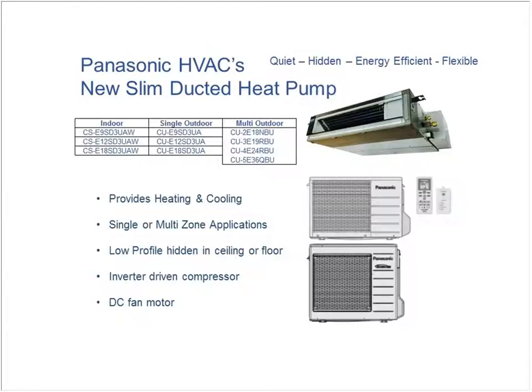Oh, and this is probably the best application. The issue with this application, though, is there's a cost issue. This is a slim ducted heat pump, and we met with Lennar Homes and several builders who are actually building this into their architectural design. So what happens with the slim duct is that this has an exhaust air where the heat comes out, and now I can duct that into the different bedrooms, right? So I'll put a cover over this with a 3-duct outlet, and I can move air into 2 bedrooms and a bathroom. Let's say if I were upstairs and I wanted to put air into the 2 bedrooms and a bathroom, I can duct that right in there.